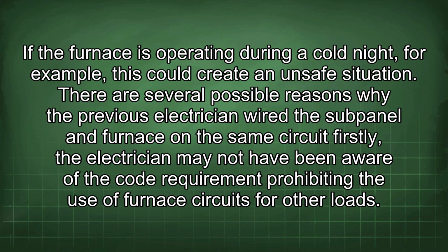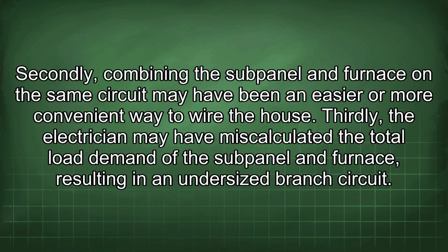There are several possible reasons why the previous electrician wired the subpanel and furnace on the same circuit. Firstly, the electrician may not have been aware of the code requirement prohibiting the use of furnace circuits for other loads. Secondly, combining the subpanel and furnace on the same circuit may have been an easier or more convenient way to wire the house. Thirdly, the electrician may have miscalculated the total load demand of the subpanel and furnace, resulting in an undersized branch circuit.